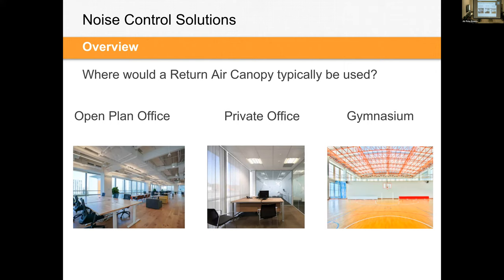But if you're ever working in an indoor office with one of those common returns, consider the return air canopy. It works very, very well. Why does it work so well? When you look at an office like this, these ceiling tiles, and the same ones in front of us here, are designed and sold with specific acoustic criteria. They either have NRC or STC ratings, which basically means they have a sound absorption property or a sound blocking property. And people will go to great lengths to buy very expensive ceiling tiles, pressed fiberglass or mineral wool. But when you put in a large open return grill, it limits the entire ceiling's what they call CAC, ceiling attenuation class. It makes this entire ceiling a weak link because of that open return.